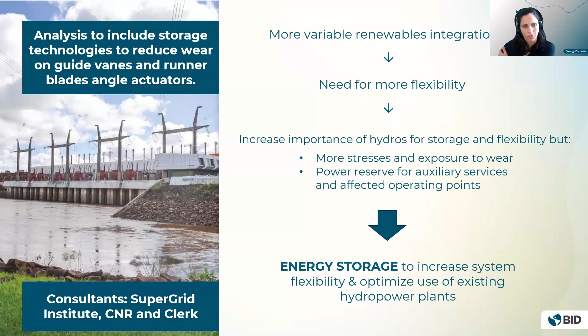Next one, please. The Salto Grande hydroelectric complex is one of the main frequency regulators in the interconnected Argentina and Uruguay systems, which has a high share of variable renewable energy. Salto Grande's Kaplan turbines regulate frequency by adjusting their power production through a combined action, the double regulation of the guide vanes and the runner blades angle.